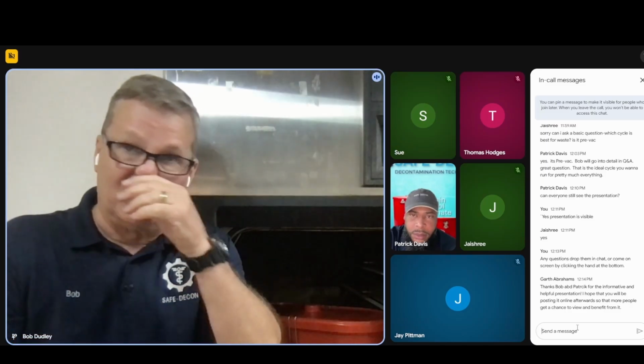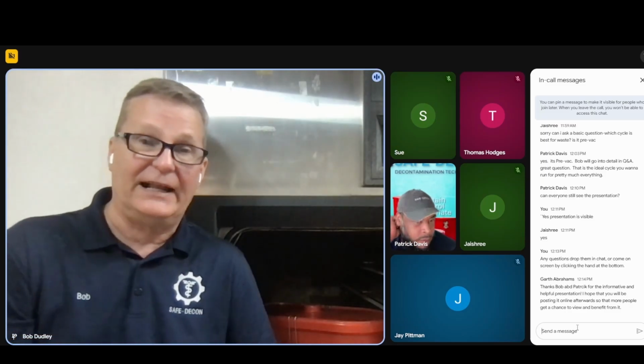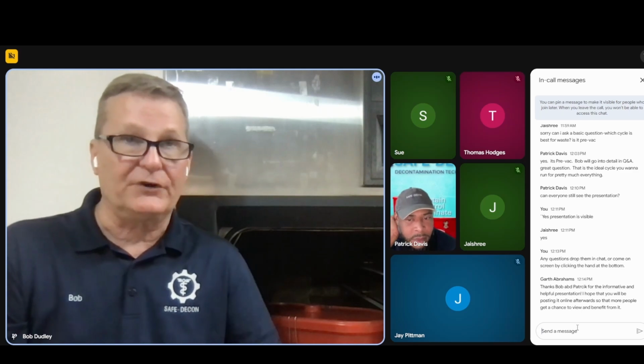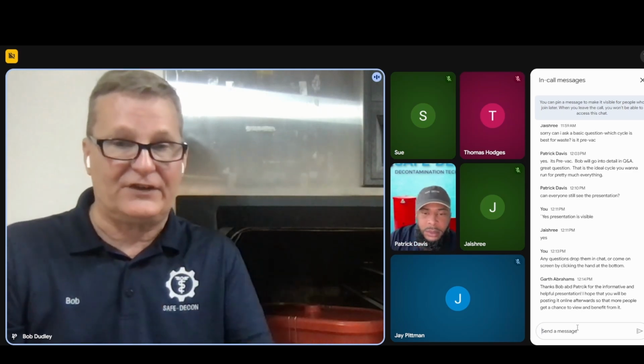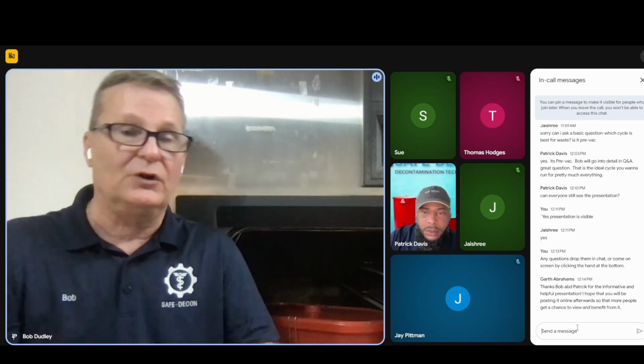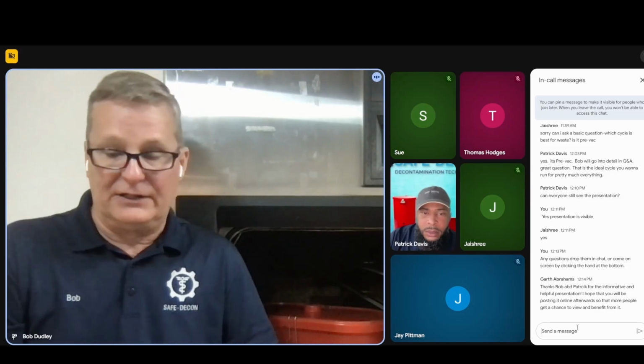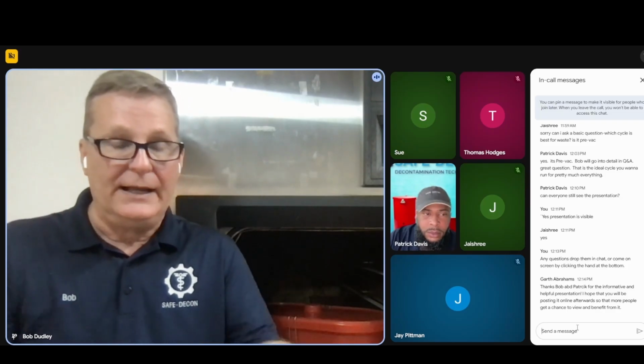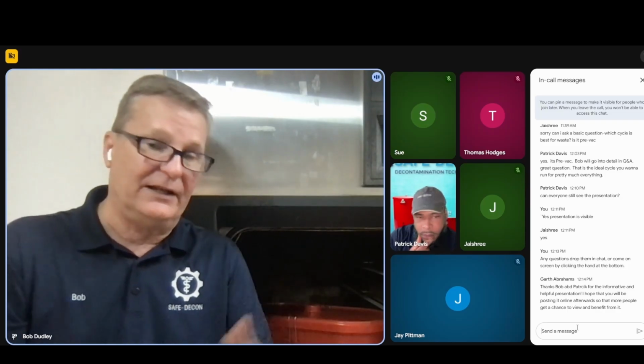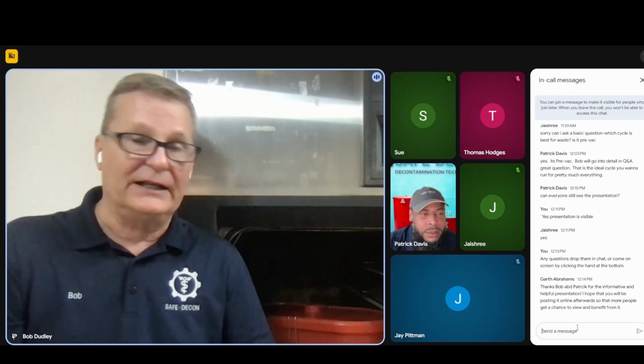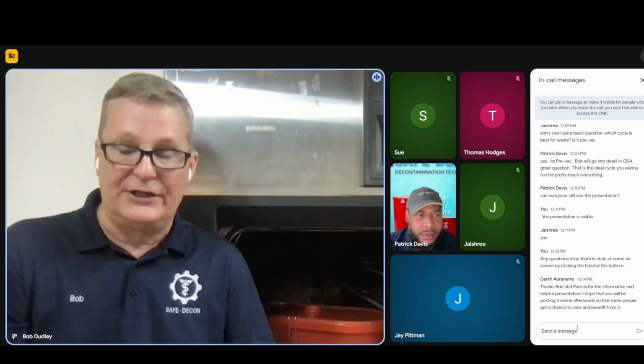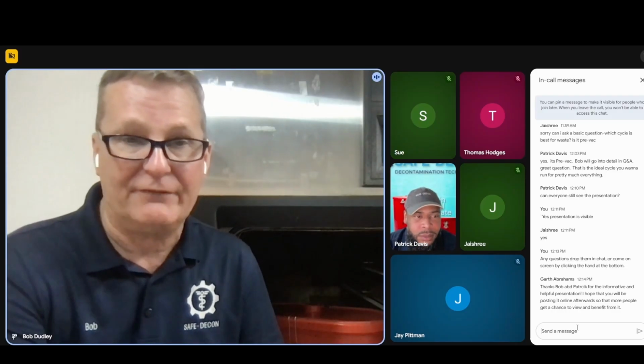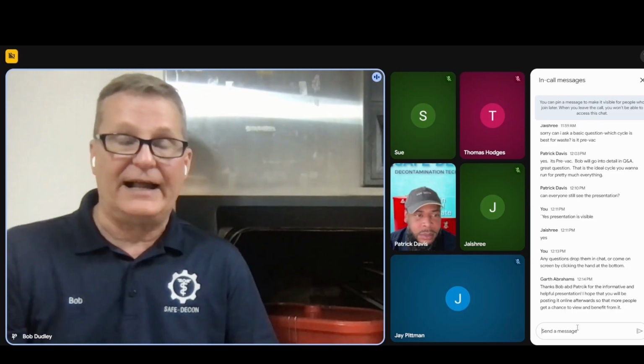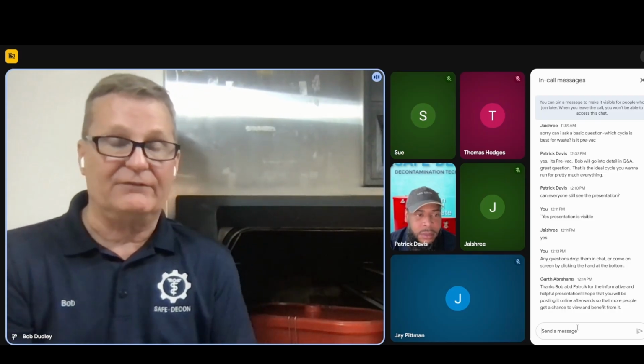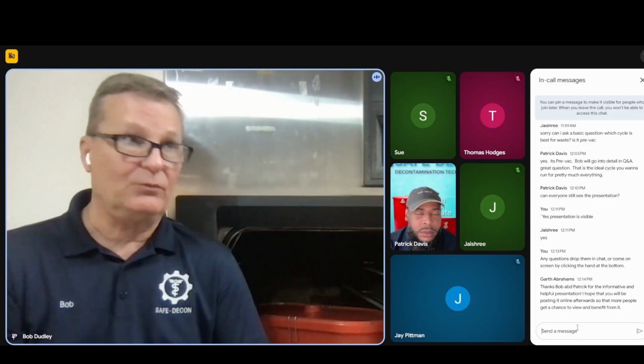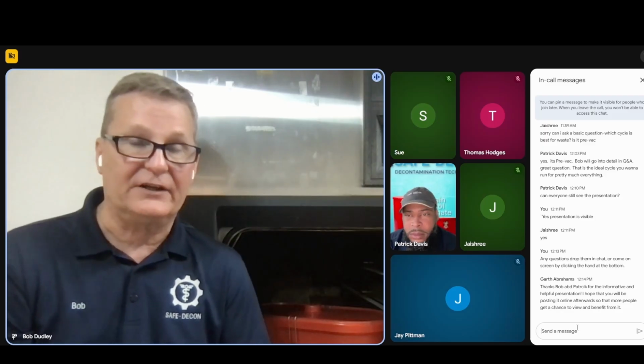And again, people have a misunderstanding about steam and its purpose. Steam is not what kills, it's the heat, but the steam is what pulls that heat in. Steam is attracted to cool. It's going to pull that heat in, but the minute it condenses, you're going to get that block. And that's why you get more failures out of the gravity and the liquid cycles than you do with a pre-vac. If you look at the data and the information that I have, the pre-vac was way more effective.